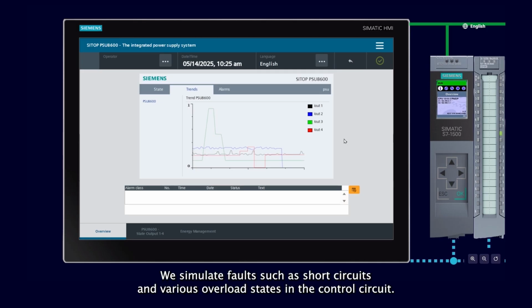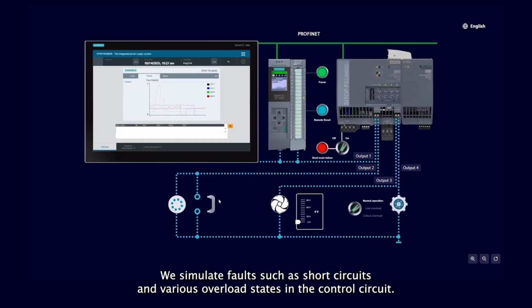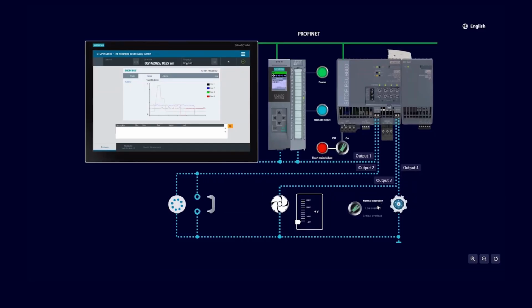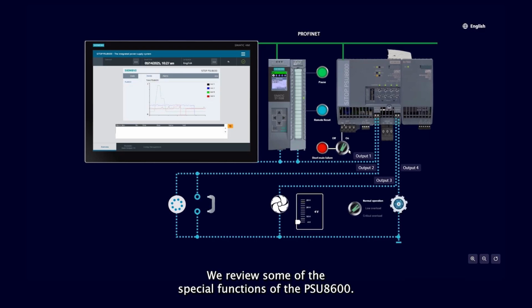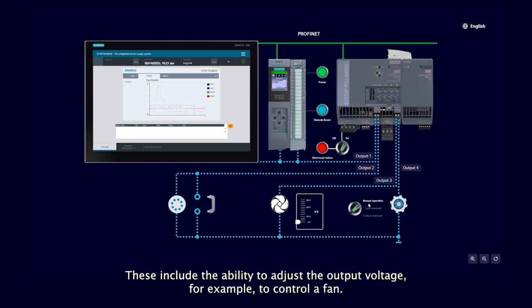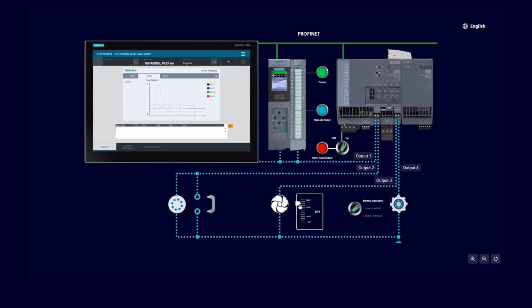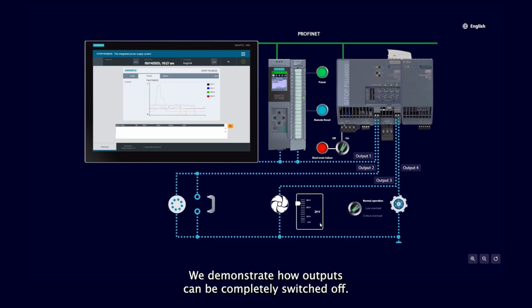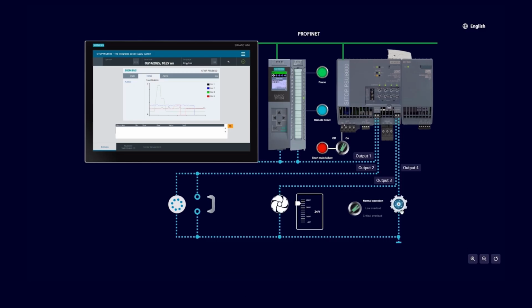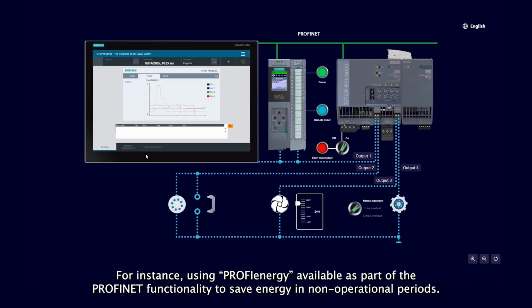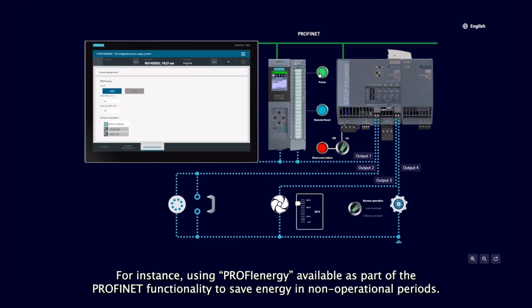We simulate faults such as short circuits and various overload states in the control circuit. We also simulate power failures. We review some of the special functions of the PSU8600. These include the ability to adjust the output voltage, for example, to control a fan. We demonstrate how outputs can be completely switched off, for instance, using Profi Energy, available as part of the Profinet functionality, to save energy in non-operational periods.